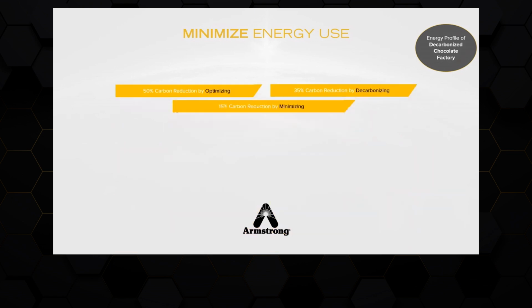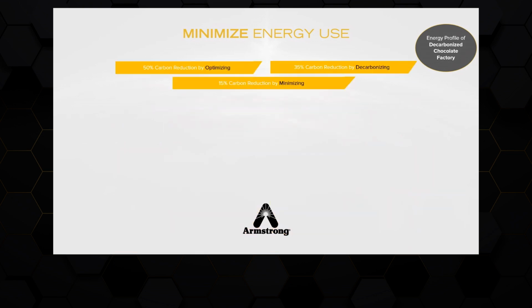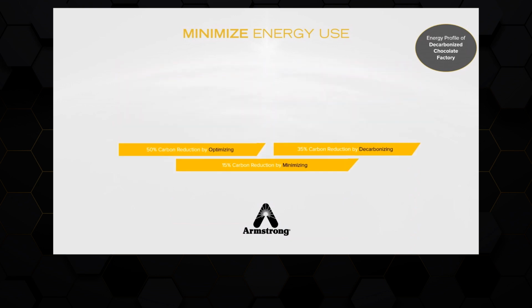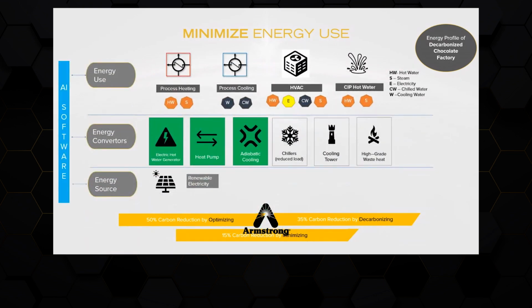So at this Skywalker plant, more than half of the carbon footprint, as we know, was reduced by optimizing and minimizing. The remaining half or less than half was met by decarbonizing the energy sources. The process utility changes like de-steaming and custom-designed technology alternatives like heat pump and adiabatic cooling help to reduce energy demand substantially, leaving only half or less than half of current thermal demand that needs to be decarbonized. We strongly believe that thermal mapping and optimizing is really a no-regrets first step for building organizational momentum and confidence in this journey towards decarbonization.